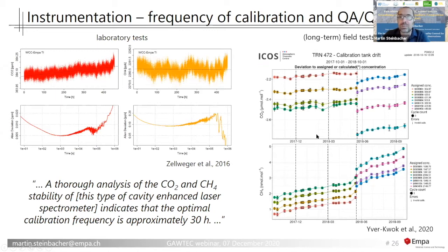This is again from the ICOS network: 1 year of calibration, 4 different calibration gases for 1 year. There was a change in the calibration tanks here in summer 2018. Here you see the drift of the instrumentation. This is the difference of the measured value to the assigned value. That means the analyzer measures about 1 to 2 ppb higher than the reality. But if you know that and you track that, you can easily correct for this. And here calibrations are only taking place every 2 to 3 weeks.